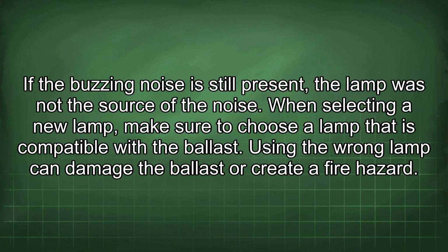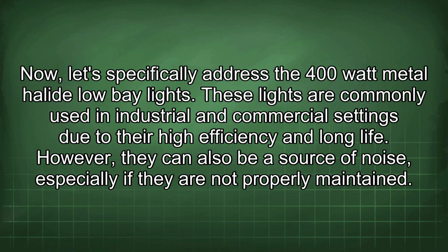When selecting a new lamp, make sure to choose a lamp that is compatible with the ballast. Using the wrong lamp can damage the ballast or create a fire hazard. Now, let's specifically address the 400-watt metal halide low bay lights. These lights are commonly used in industrial and commercial settings due to their high efficiency and long life. However, they can also be a source of noise, especially if they are not properly maintained.